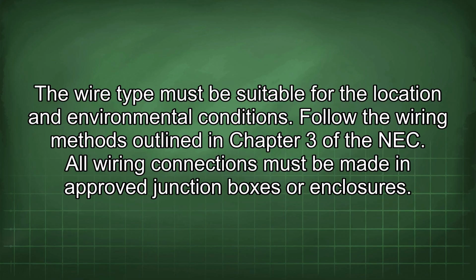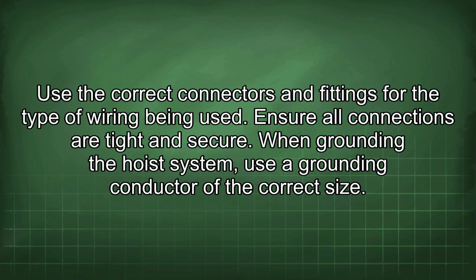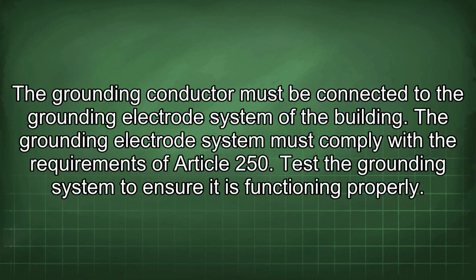All wiring connections must be made in approved junction boxes or enclosures. Use the correct connectors and fittings for the type of wiring being used. Ensure all connections are tight and secure. When grounding the hoist system, use a grounding conductor of the correct size. The grounding conductor must be connected to the grounding electrode system of the building. The grounding electrode system must comply with the requirements of Article 250. Test the grounding system to ensure it is functioning properly.